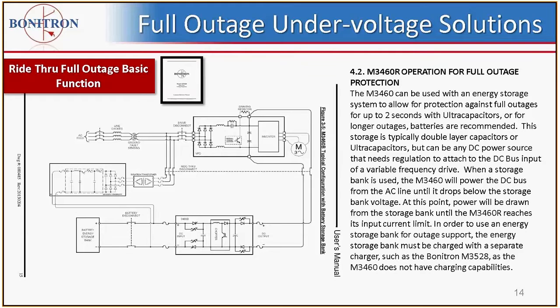And once again, it will keep boosting until either the 2-second limit is reached in the sag ride-throughs if you're using ultracapacitor energy storage, or until the battery is down to a certain level, or the ride-through event is over and the bus threshold returns to normal because the utility power is back to normal. The ride-through once again turns off, it being a passive device.